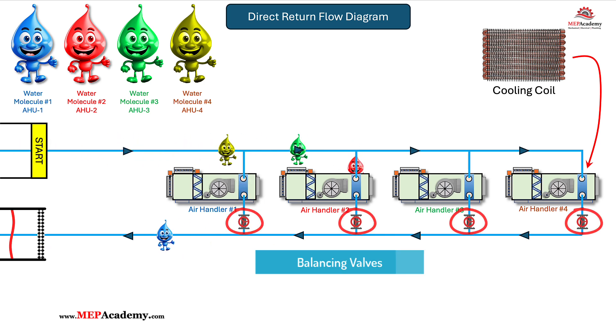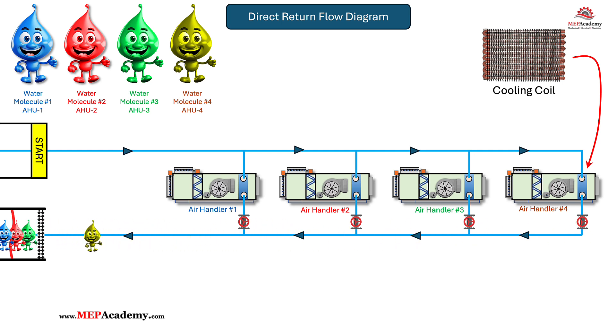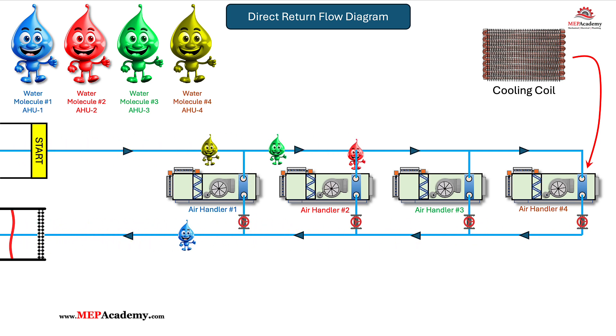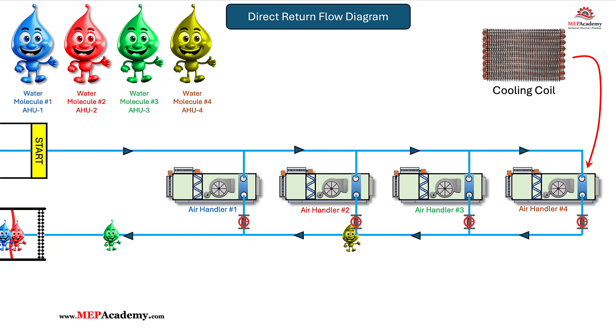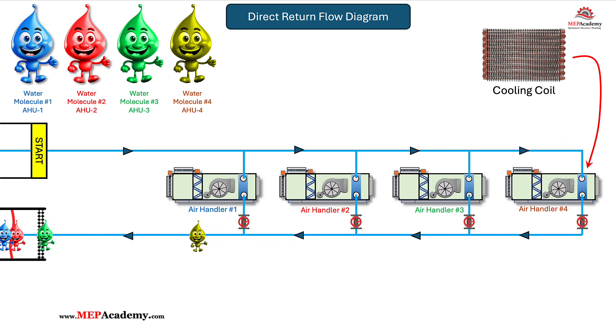This is why balancing valves are often added to create additional pressure drops to equalize each piping circuit. Direct return is often considered simpler and more cost-effective to install, as it requires less pipe and can be laid out with fewer complex fittings. The layout can differ with all coils in a straight line, as shown in this piping diagram, which makes it easier to see how this works.